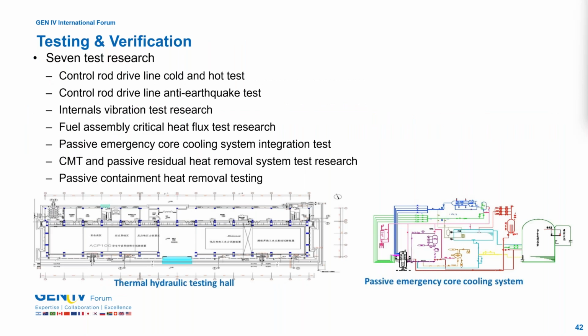We have done a lot of testing and verification in our institute. There are 7 testing research projects that have been done. They include control rod drive line cold and hot test, control rod drive line anti-earthquake test, internal vibration testing, fuel assembly critical heat flux testing, passive emergency core cooling system integration testing, CMT and passive residual heat removal system, and passive containment heat removal testing.